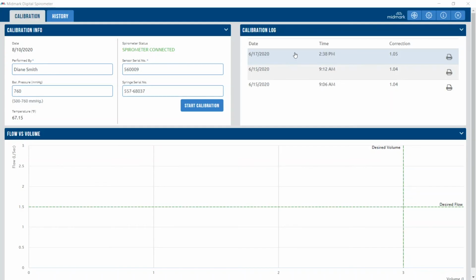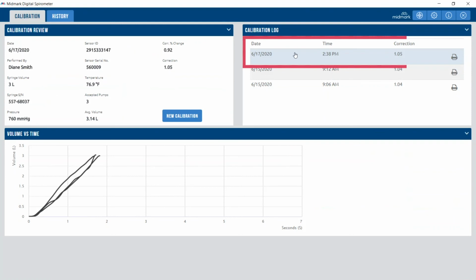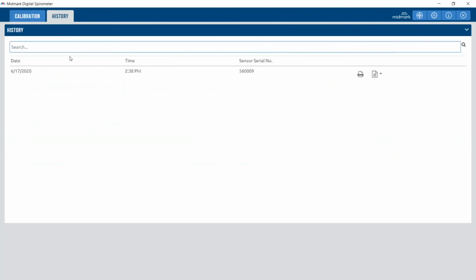IQ Manager software contains a calibration log that retains all calibrations performed for the spirometer. To view and/or print the calibration log, go to the calibration screen and click on a calibration from the calibration log, or select a device from the Device History tab on the calibration screen.